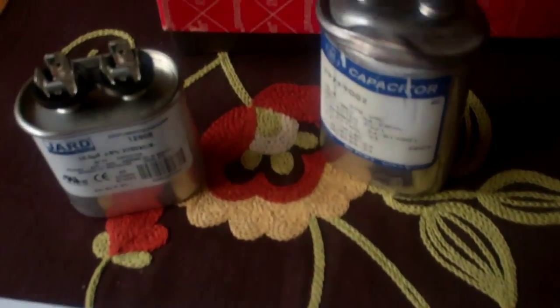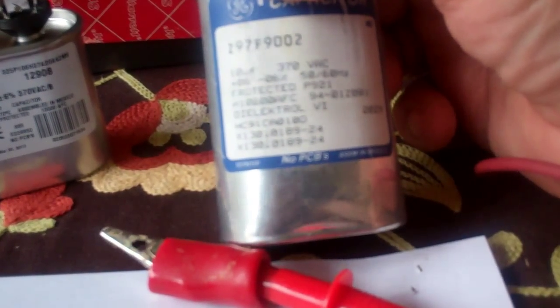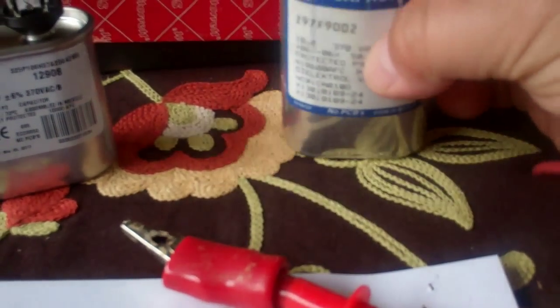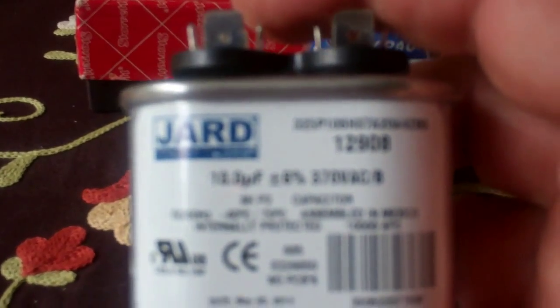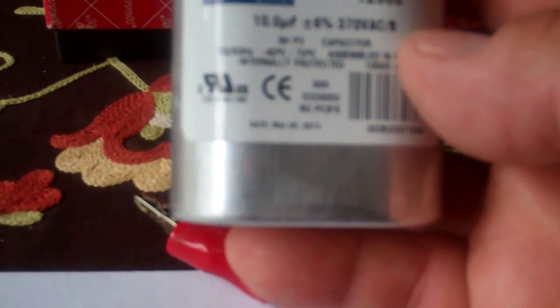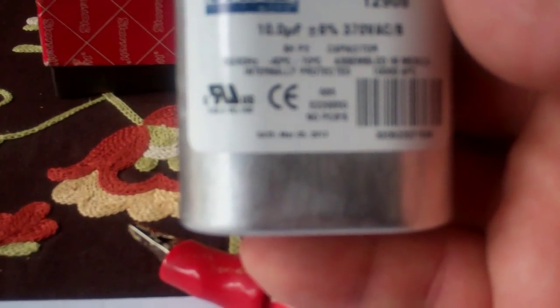Now we're going to look at the capacitor. Here's the old one and the new replacement. Even though it's smaller, it's what's on the label that matters. And what we were looking for was 10 microfarad, 370 volt AC, plus or minus 6%, 60 cycles, 60 hertz. So 60 cycles per second. And what we got is exactly the same thing. 10 microfarad, plus or minus 6%, 370 volt AC, 60 hertz, 50 slash 60 hertz. So we can check that.